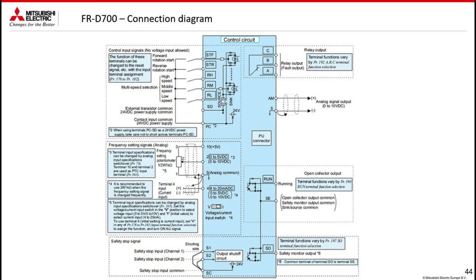Inside the inverter, there is also a 24 volt power supply where PC is the positive 24 volt and SD is the common, therefore 0 volt. In fact, in positive logic, I take the positive from the PC to close the different signals. If an external 24 volt power supply is used, it will be necessary to connect the 0 volt of the external power supply with the SD so that the signals can be correctly read.